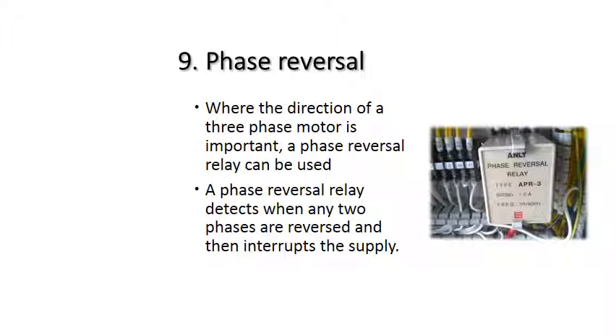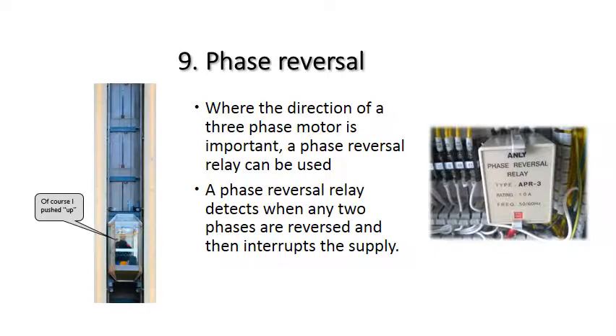There's a whole variety of reasons why or how two phases could get changed over, depending on the circumstances. One might be that someone's crashed into a pole out in the street, and when the power supply authority come and replace the overheads, they somehow cross two phases over to where they used to be. There's a whole bunch of reasons. So if it's important that the motor goes the right way, you should use one of these phase reversal relays.